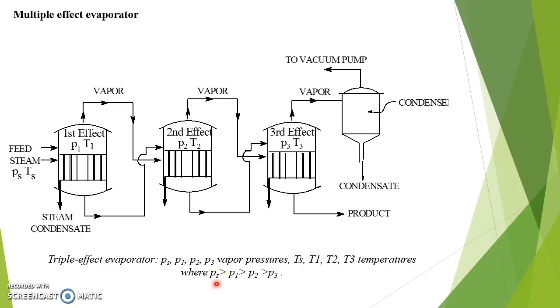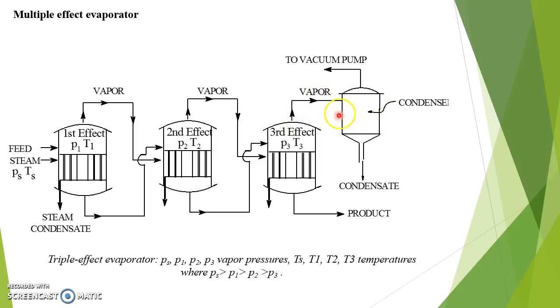The vapor pressure of steam PS is greater than the pressure in the first effect evaporator, which is greater than the pressure in the second effect evaporator, and similarly greater than the third effect evaporator. In this diagram all evaporators are connected with each other. The vapor from the first evaporator is used as a source of steam for the second evaporator, and similarly from the second evaporator it is used as a steam source for the third effect evaporator. From the third effect evaporator the vapor goes to the condenser and then to the vacuum pump, and the condensate is collected from the bottom of the condenser.